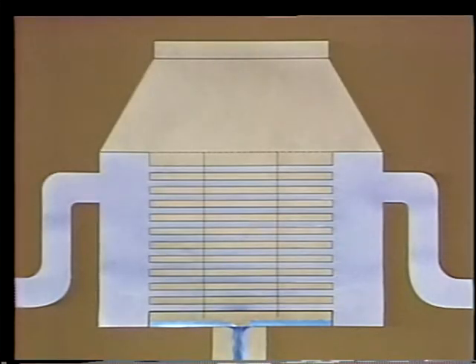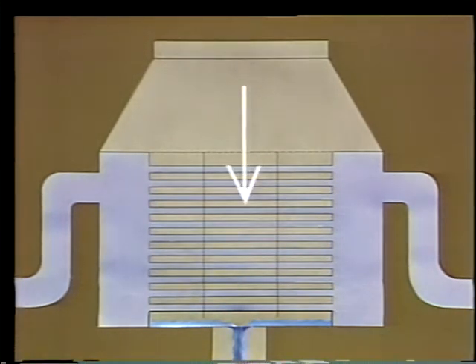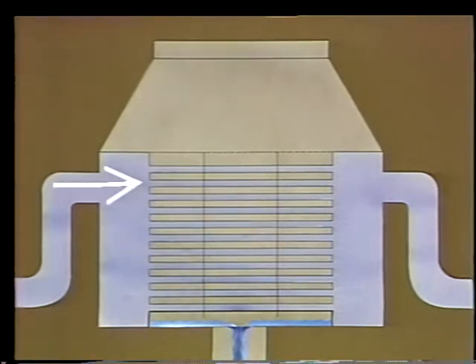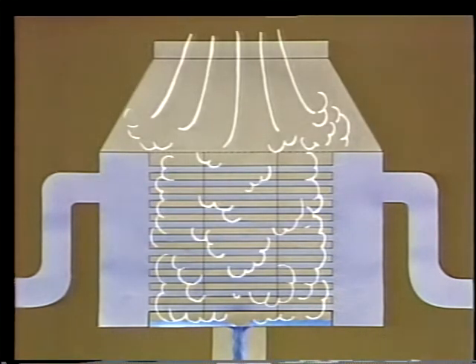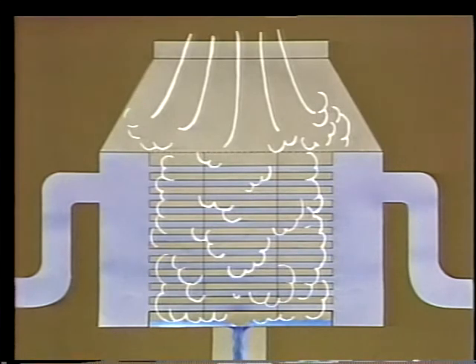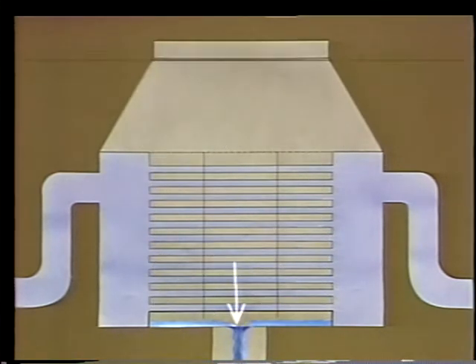A condenser is a heat exchanger which converts a vapor back to a liquid. The condenser on a turbine takes steam directly from the turbine's exhaust and runs it over a bundle of tubes. The tubes have cold water being pumped through them from a source like a cooling pond, a river, a lake, or an ocean. As the steam passes over the tube bundle, it gives up its heat to the cooling water.